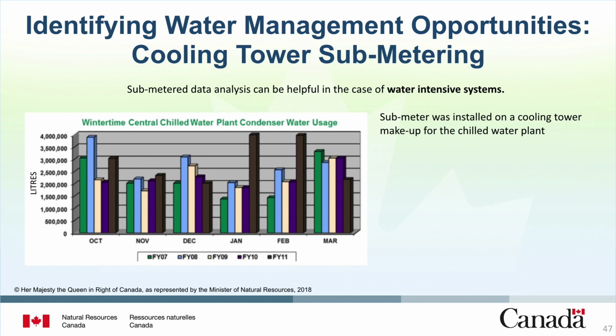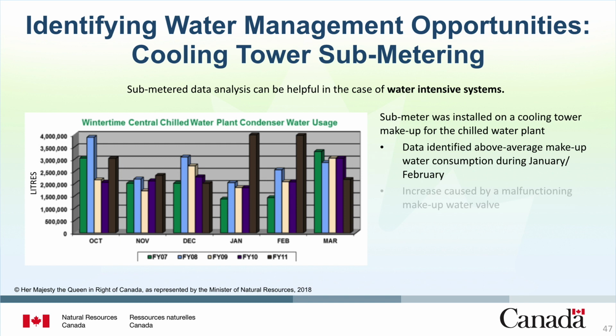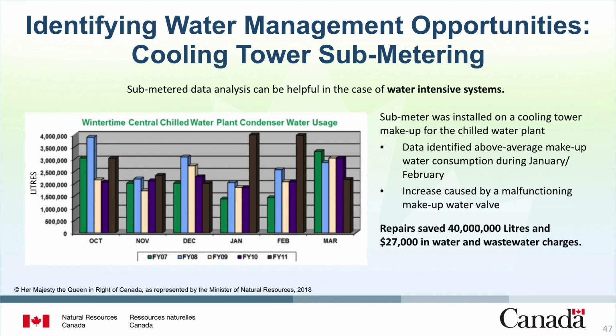By evaluating water use data provided by the sub-meter, the energy manager noticed above-average makeup water consumption occurred during January and February. Further investigation revealed that the increase was caused by a malfunctioning makeup water valve. Identifying and repairing the malfunctioning valve efficiently using sub-metering data saved the site 40 million liters of water and $27,000 in water and wastewater charges annually.